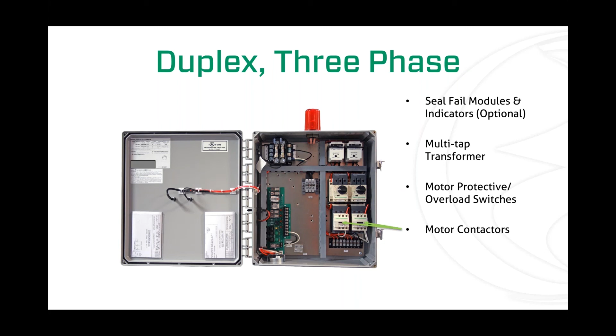This one does not use a circuit board. You can see there's a number of relays across the top there, so this is using good old-fashioned relays for hardwired logic. It's very possible you're going to run into an engineer out there that prefers this type of system. And the reason he does is because it doesn't have a control board in it, doesn't have a circuit board. With relays performing the logic like this, there's more wiring, there's more components.